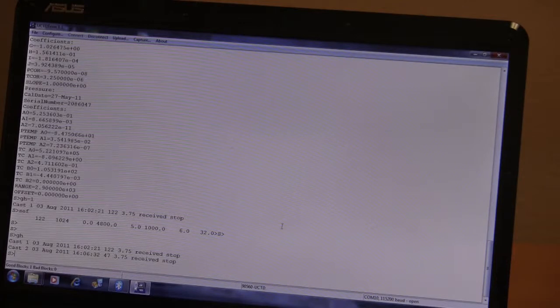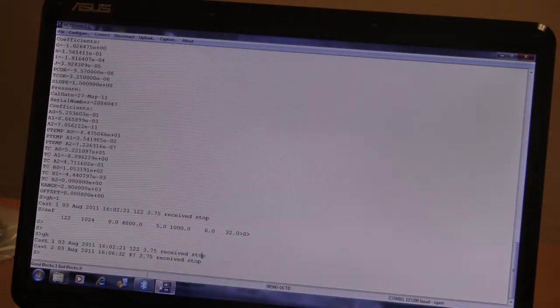And basically it shows you cast 1, recorded on August 3rd, and the time, the number of samples in that profile, the battery voltage when it was recorded, and in this case it also tells you why the recording stopped. It's because I cycled the magnetic plug rather than let the probe continue to record for a full 100 seconds. So in order to get the data off the probe, we use the upload command.